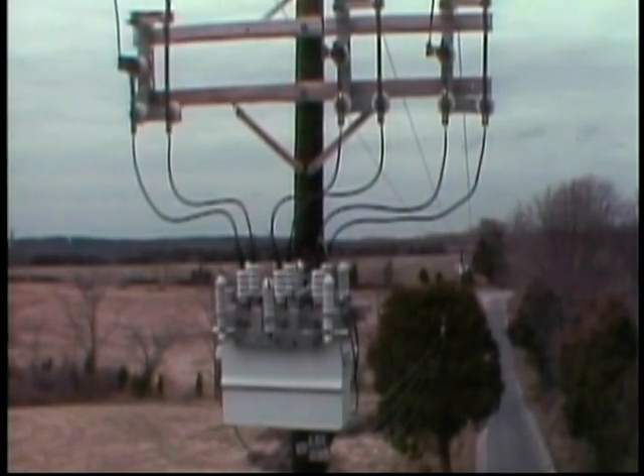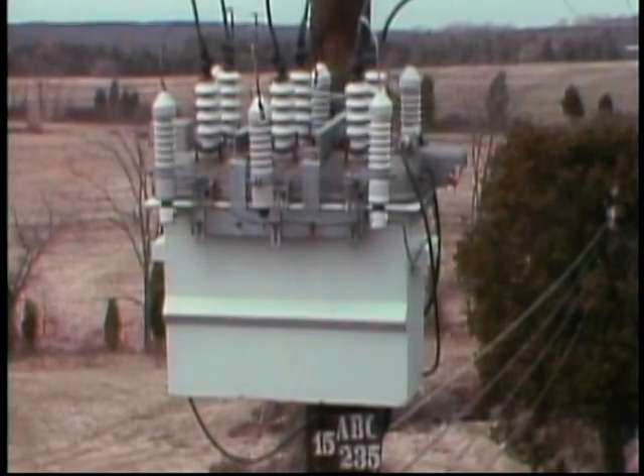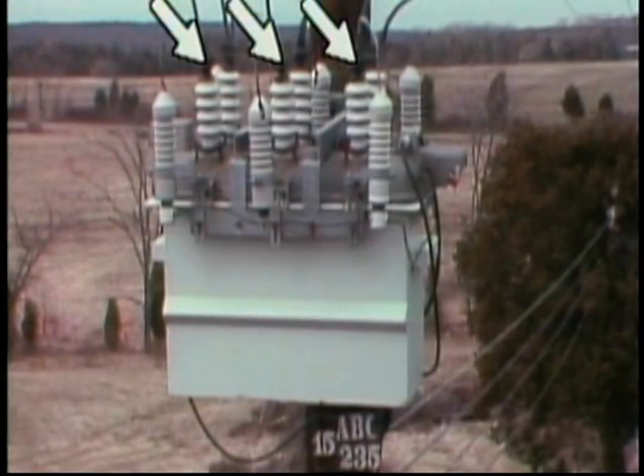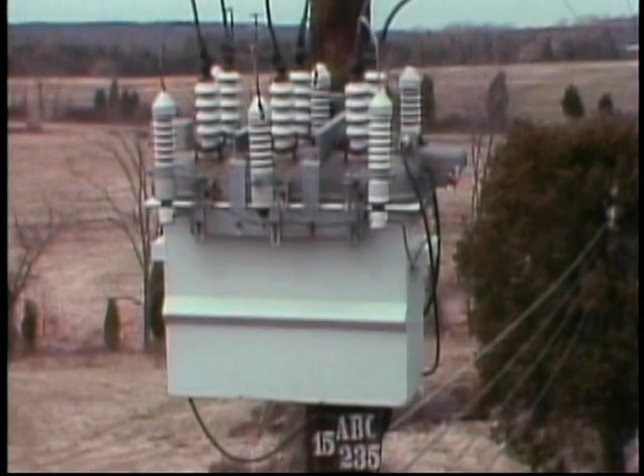A three-phase recloser may look a little different. Here, it's a rectangular device with 3 pairs of bushings. It also has a single operating handle to open or close all 3 phases simultaneously.